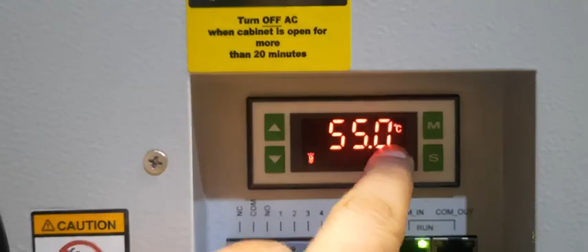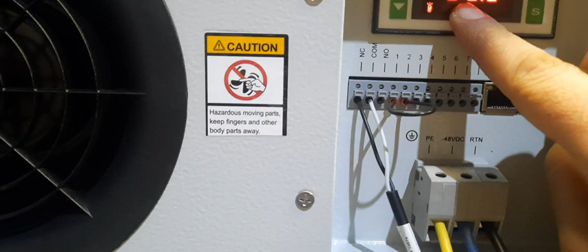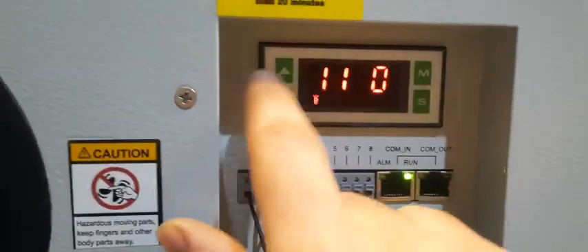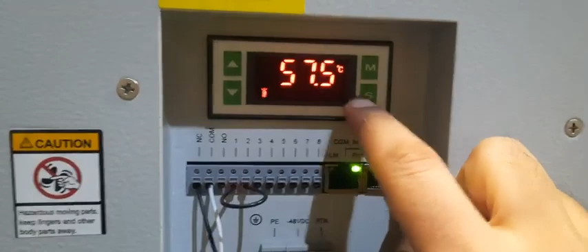S, it's 55 centigrade. You can change it as per your design. If you need more, you press 57 centigrade, then your temperature will increase before the high temperature alarm is active. Press. Now Zamil asks me what the password is. The password is 1, enter, 1, enter, 1, enter, 1 and enter. It's 57. Okay, go back.